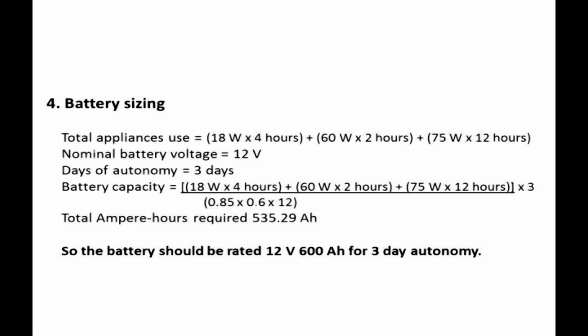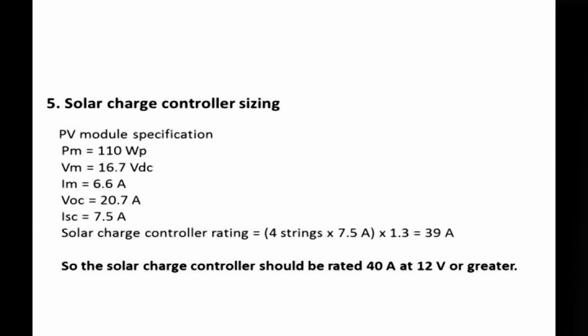Step 4: Battery sizing. Total appliance use = (18 W × 4 h) + (60 W × 2 h) + (75 W × 12 h). Nominal battery voltage = 12 V; days of autonomy = 3 days. Battery capacity = [(18 W × 4 h) + (60 W × 2 h) + (75 W × 12 h)] × 3 ÷ (0.85 × 0.6 × 12) — total ampere-hours required = 535.29 Ah. So the battery should be rated 12 V, 600 Ah for three-day autonomy. Step 5: Solar charge controller sizing. PV module spec: Pm = 110 Wp, Vm = 16.7 VDC, Im = 6.6 A, Voc = 20.7 V, Isc = 7.5 A. Controller rating = 4 strings × 7.5 A × 1.3 = 39 A. So the solar charge controller should be rated 40 A at 12 V or greater.